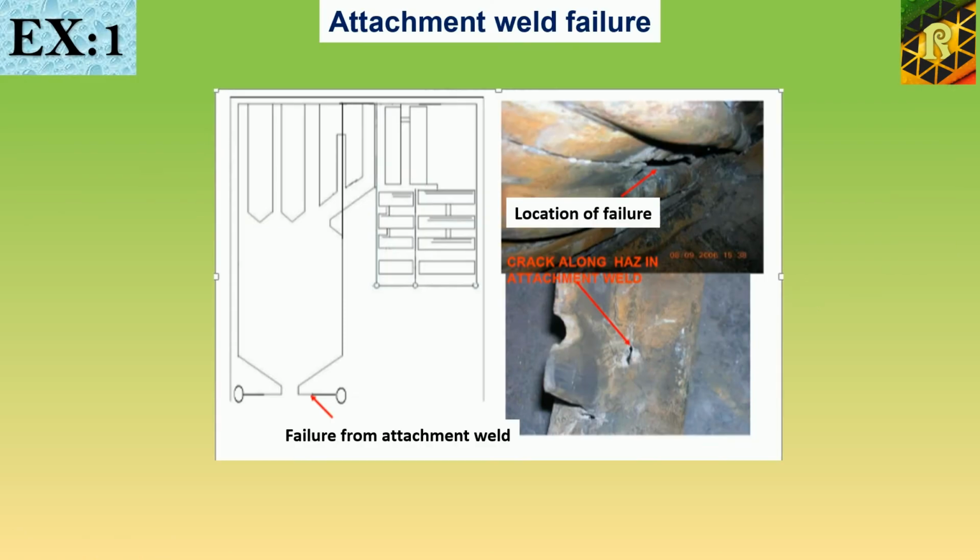There is another example of attachment weld failure. Here in this case, a crack developed along the heat affected zone in the attachment weld.